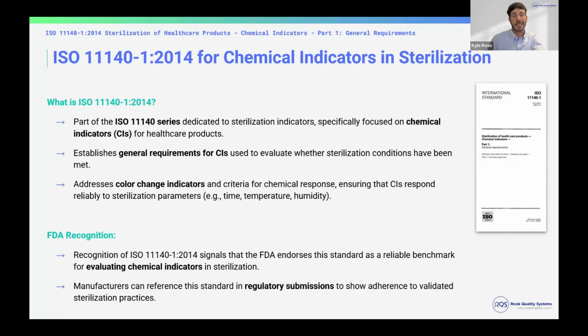Within this, they list 6 different types of chemical indicators, and you need to align with each type that aligns with your process and the indicator you're trying to determine for this use. So it touches on a few different things, such as color change indicators, how they should work, and sensitivity levels on these actual chemical indicators for sterilization. This is an older standard, so 2014, but this is the first time the FDA has recognized this standard for making sure that your chemical indicators align with this ISO standard.